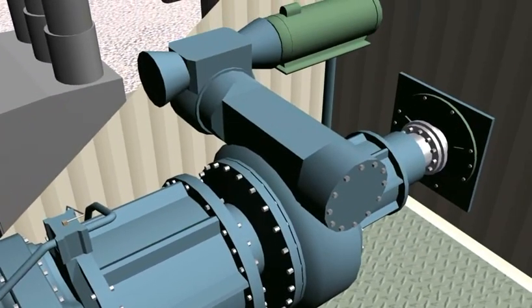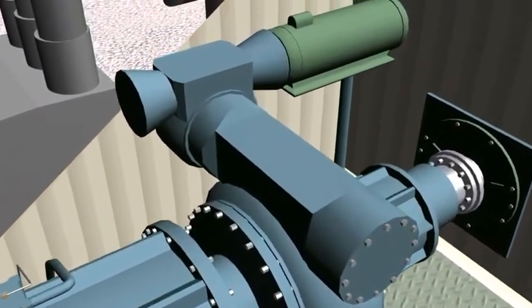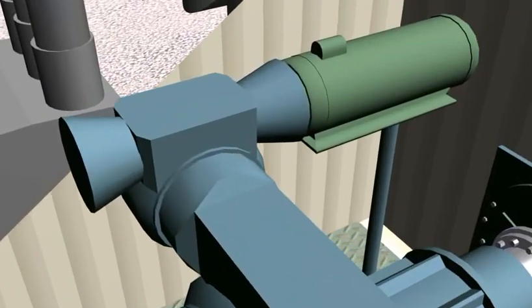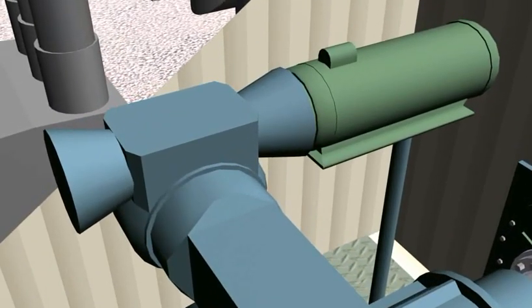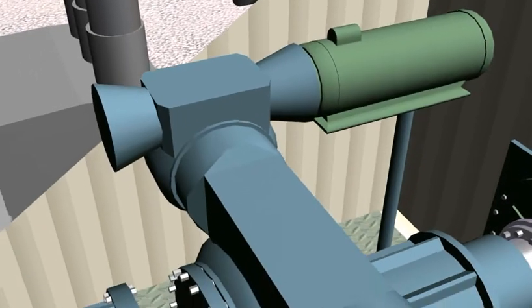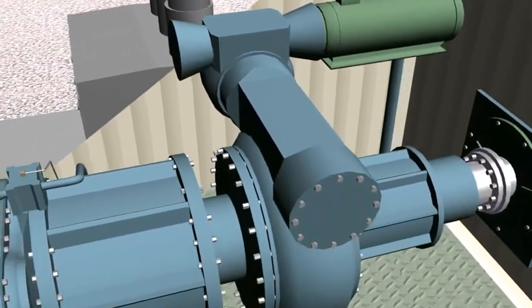The turning gear provides a slow rotation of the turbine generator shaft to help keep the rotor shaft straight. A 10 horsepower, 125 volt DC motor provides the approximate turning gear speed of 2.5 RPM.